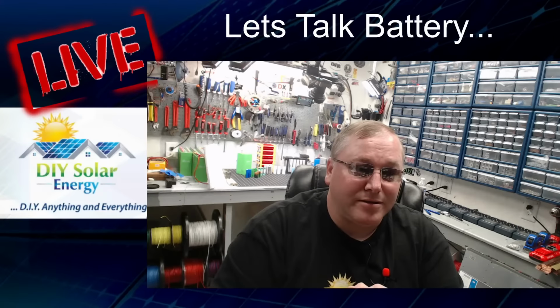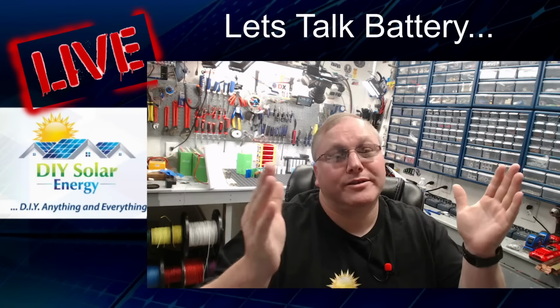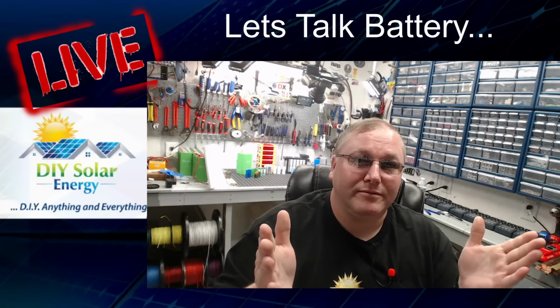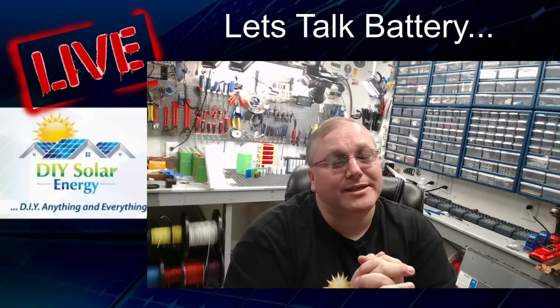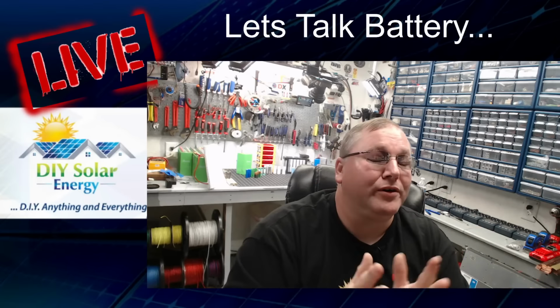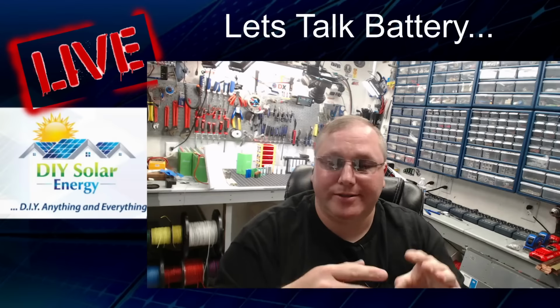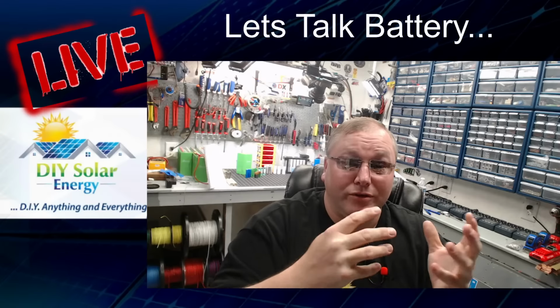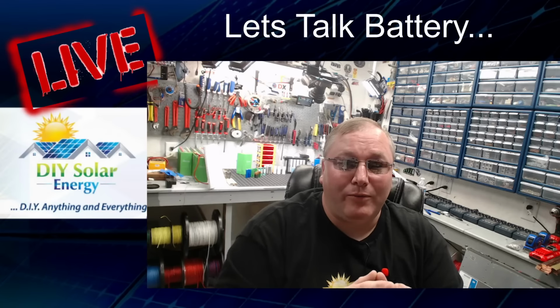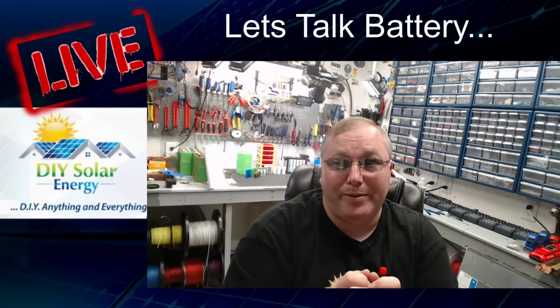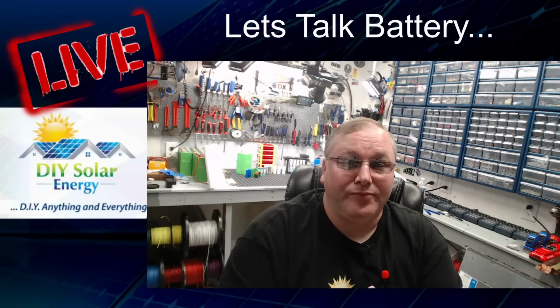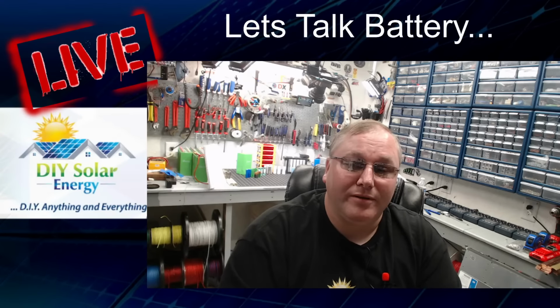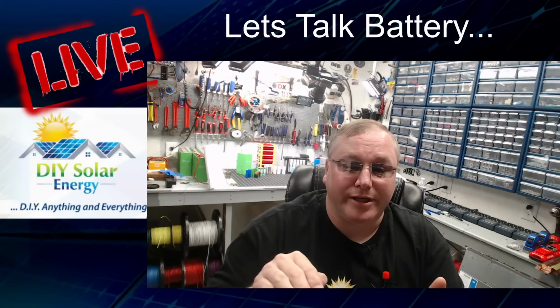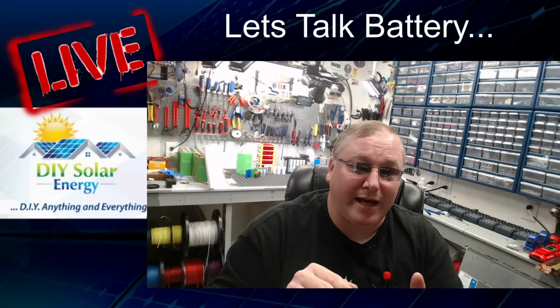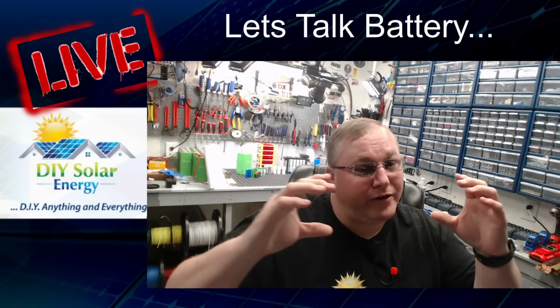Now, so we've got our 10 panels in series, which makes up, let's say each panel puts out 10 volts. So we got 100 volts at 100 amps—which isn't exactly right, but we're just going to use that for the math. Now, I want to add more panels to increase my amperage, so I want to keep my voltages close to the same. So I can add 3 parallel strings to that, which would keep me at 100 volts.